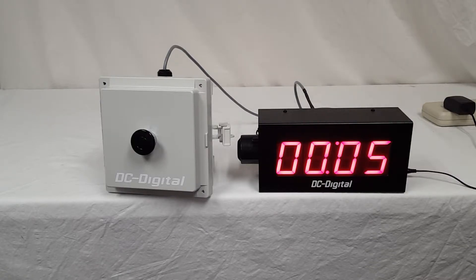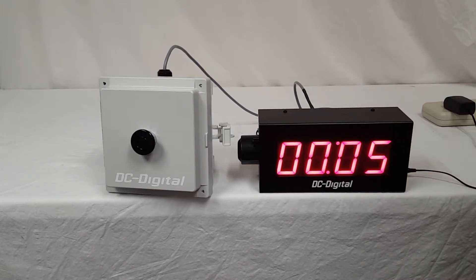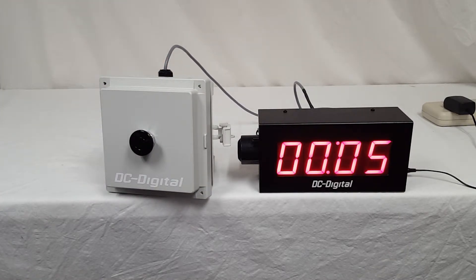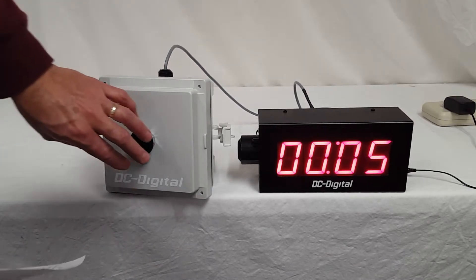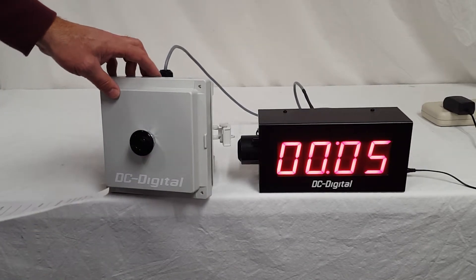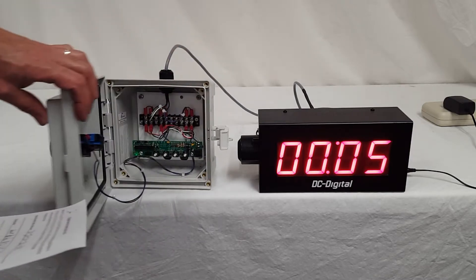It is a countdown timer with BCD, but the extraordinary thing about this is that the customer wanted the BCD remotely placed in a box — a NEMA box. This unit has just one function, whereas normally our countdown BCDs have three functions. This is a reset-to-start with a 40 millimeter industrial push button mounted to the front of the NEMA box. This is a NEMA 4X box with a hinge cover; they can latch it and put a lock on it if they want to keep people out of it.